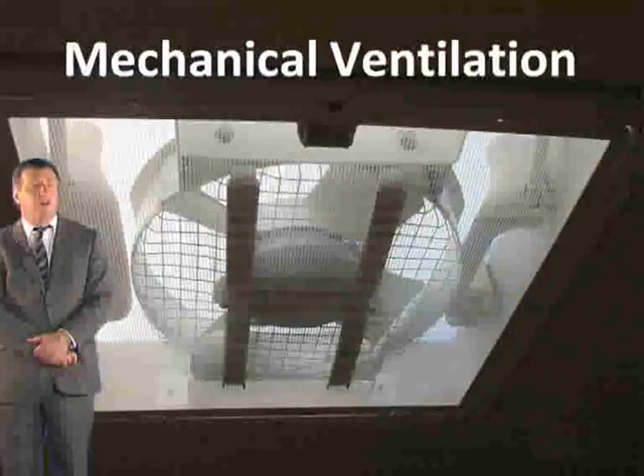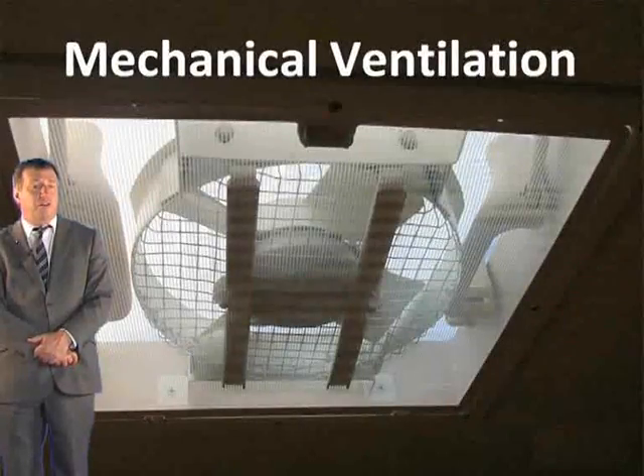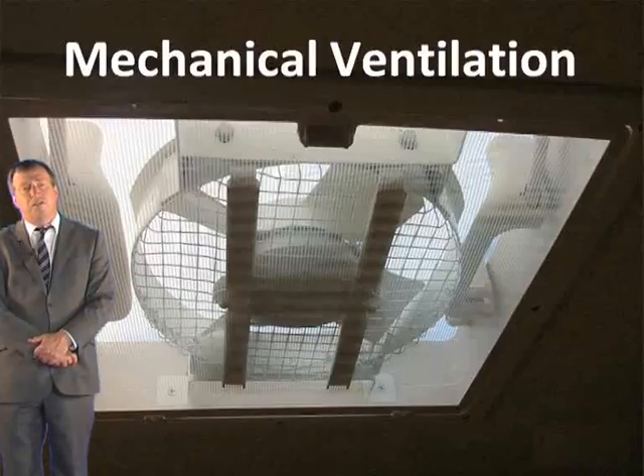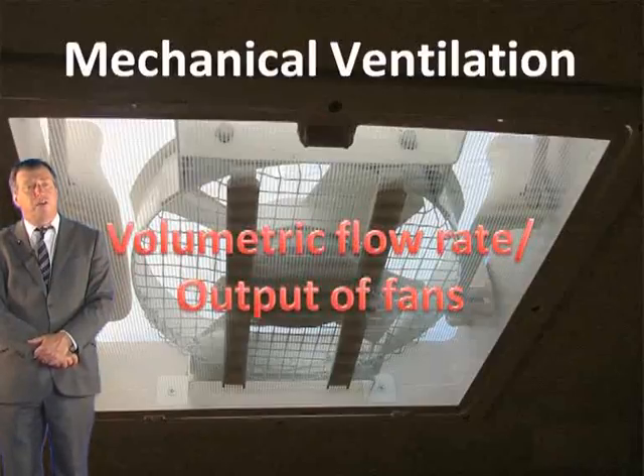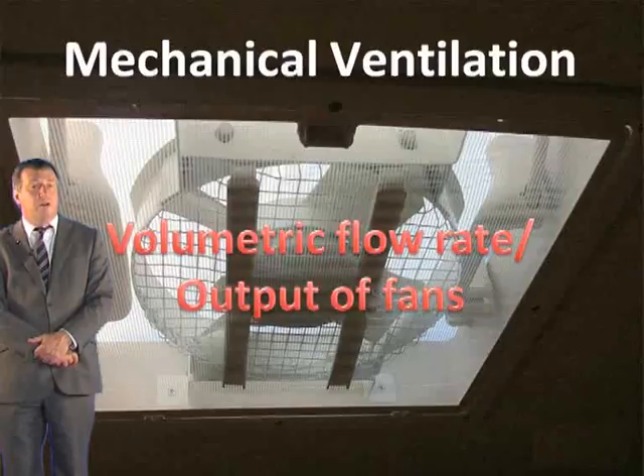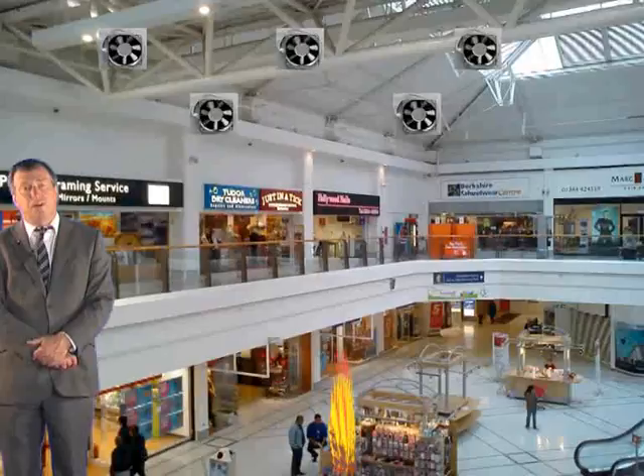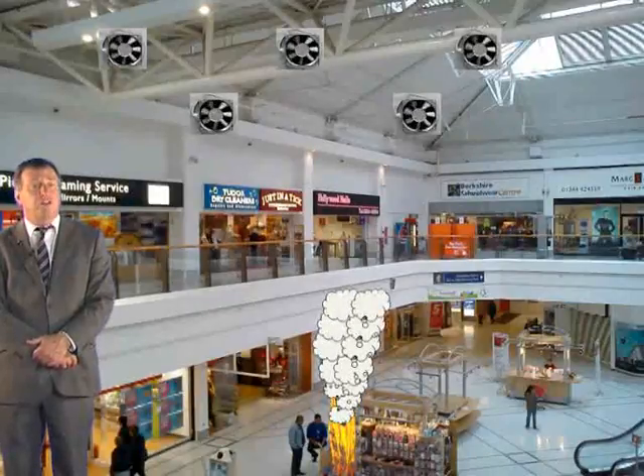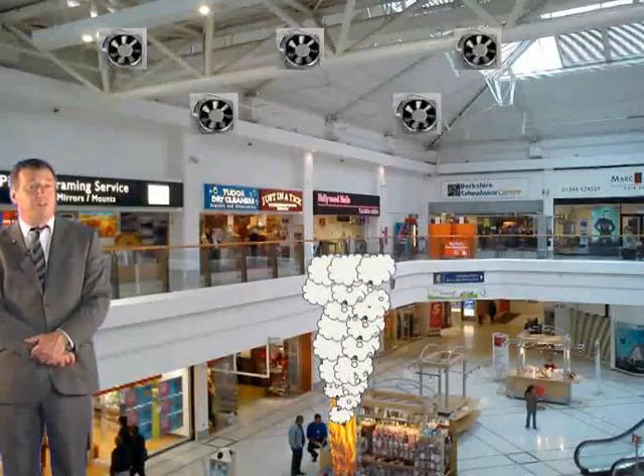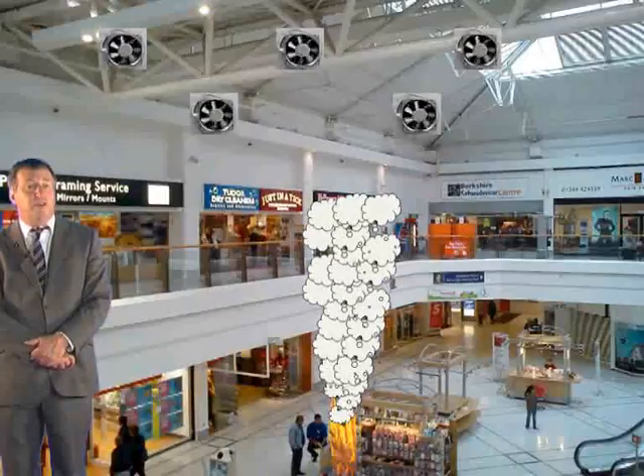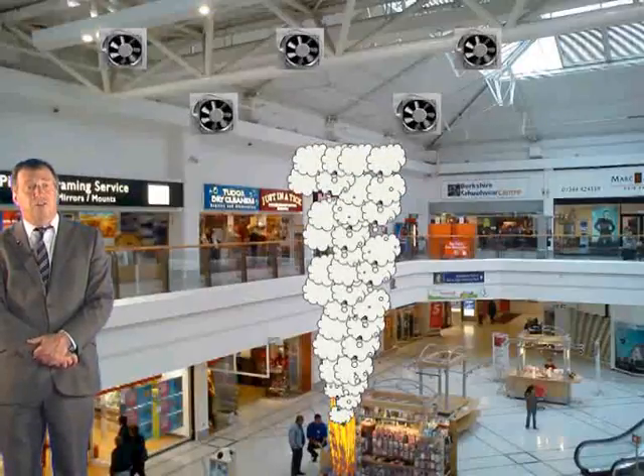Now we'll move on to look at how to determine the number of fans for mechanical ventilation. The method is not complex, and it is simply to divide the volumetric flow rate that is required per reservoir by the output from the individual fans, and then to round this up to give the minimum required number of fans. However, in some situations there is a possibility that the hot smoke will detrimentally affect one of the fans, and in such cases the design of the extraction system should allow for the loss of one fan.